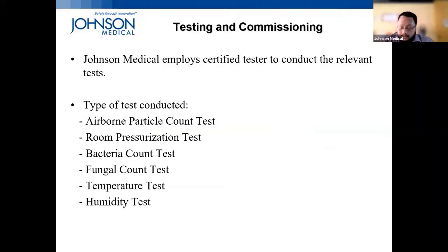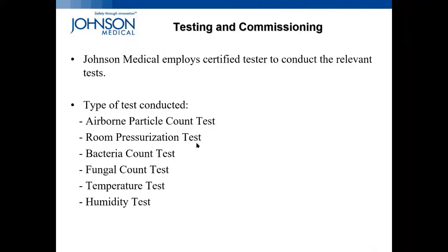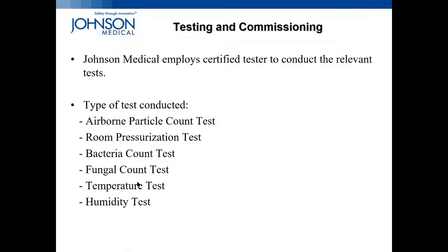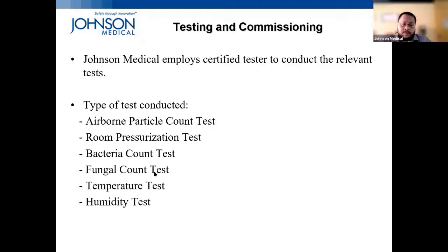So how we achieve this is during commissioning. These are the tests that we have to conform to or pass before we allow any surgical operation to be done in the OT. So we do an airborne particle count test, room pressurization test, bacteria count test, fungal count test, temperature, and also humidity test.